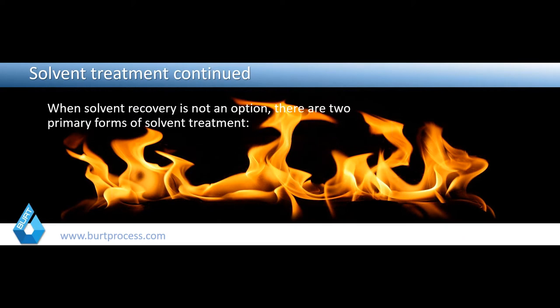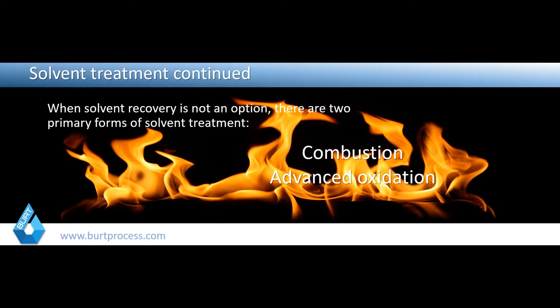Solvents are generally treated when not recovered in just two ways. Most are burned or combusted, and those gases are purged — the most efficient way of destroying different solvents. The other means is referred to as advanced oxidation process, where the solvent is exposed to high levels of UV radiation as well as ozone, breaking down the carbon structure of the solvent itself into more benign compounds like nitrogen, carbon dioxide, and water. Combustion is by far the more common approach, particularly for large quantities.